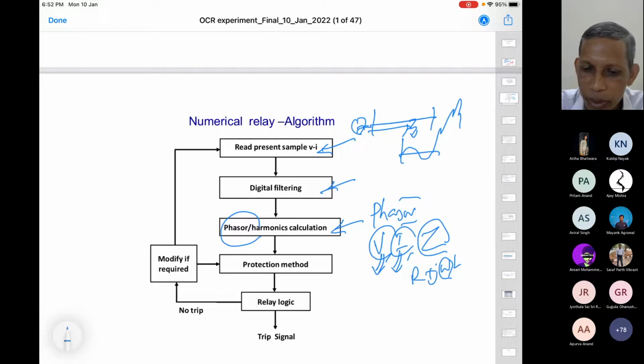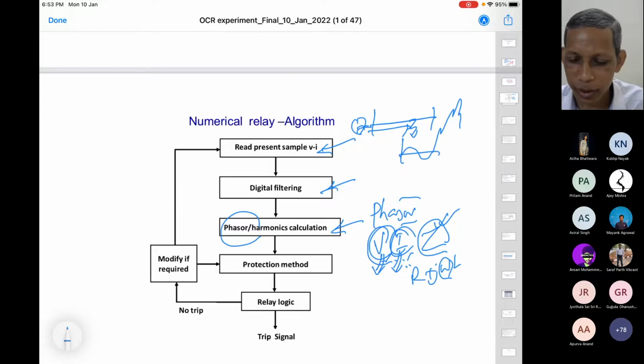So from the distorted currents and voltage, we have to extract the fundamental component, because you analyze the system in terms of impedance, R, omega, L, and so on. And therefore, you study this in fault analysis in your power system paper also. There are sequence component analysis and so on. So when you are using the concept of impedance at a particular frequency like 50 Hz in your case, we essentially require the voltage and current also at 50 Hz. During normal situation, we generally say that the voltage and currents are the fundamental component. But during fault situation, that is not correct. So you have to extract the corresponding fundamental component out of this. And that's why we are talking about the phasors also.